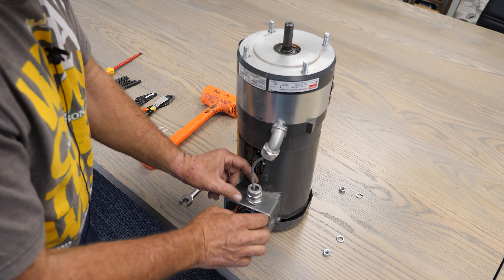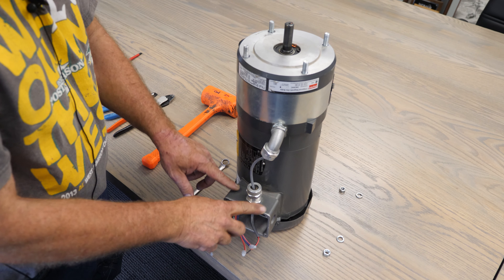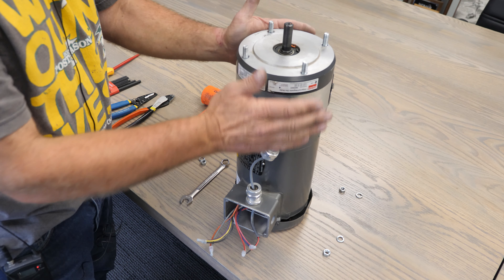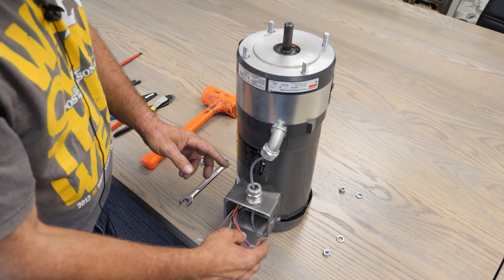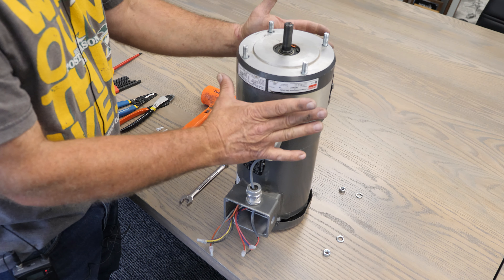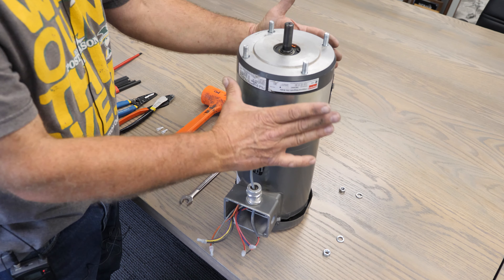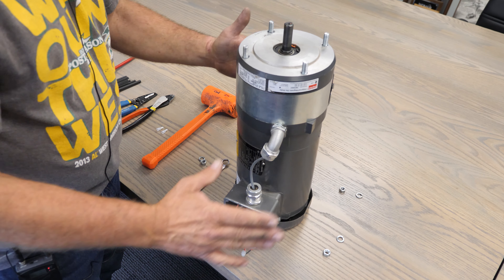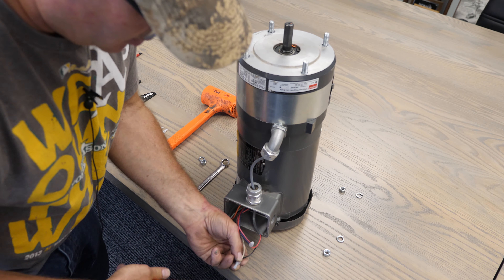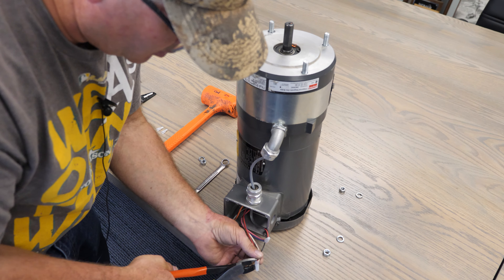Now we're going to undo the wiring. When the wire goes into the electrical box, it's going to be wired up to the high voltage on this electric motor. If the wire bypasses this box, that means it's going to be wired low voltage. So make sure — even though you have 230 — it's still going to be wired for high voltage. If it's 460, it's also wired for high voltage. I'll explain that as we hook this back up. Now I'm going to take my crimpers and take these off. Sometimes they don't come off and you just have to cut the wires.